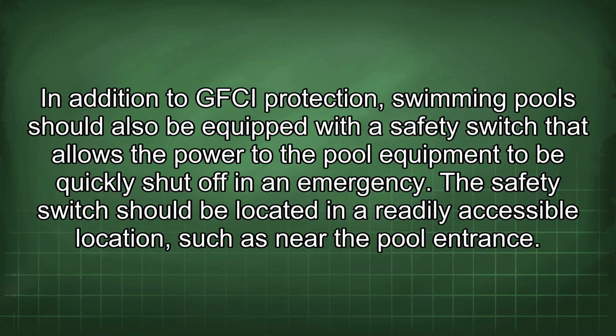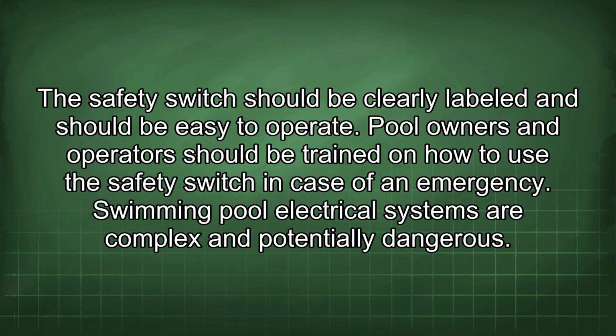In addition to GFCI protection, swimming pools should also be equipped with a safety switch that allows the power to the pool equipment to be quickly shut off in an emergency. The safety switch should be located in a readily accessible location, such as near the pool entrance. The safety switch should be clearly labeled and should be easy to operate. Pool owners and operators should be trained on how to use the safety switch in case of an emergency.